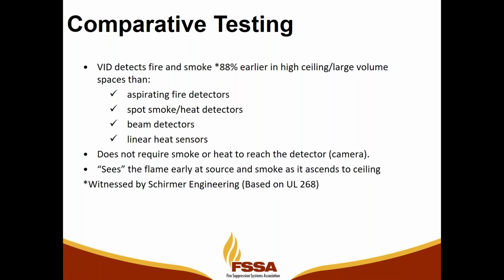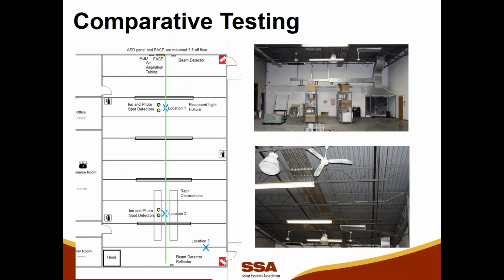So in this 18-foot ceiling application, video analytics detected the fire and smoke 88% of the time faster than the other technologies. In this case, the only location where video analytics was second was in the upper right-hand image. There was a fire between the racks. The other technologies were at the ceiling. As the smoke rose, the video analytics camera in the corner had to wait for the smoke to break the top of the racks before it could start analyzing the image. The other detection technologies detected before it.